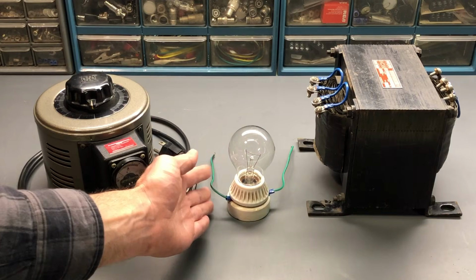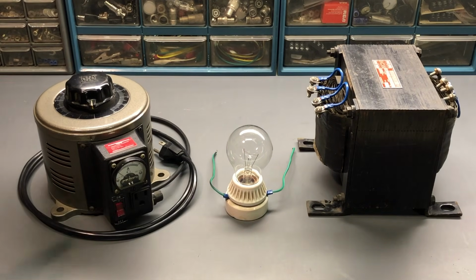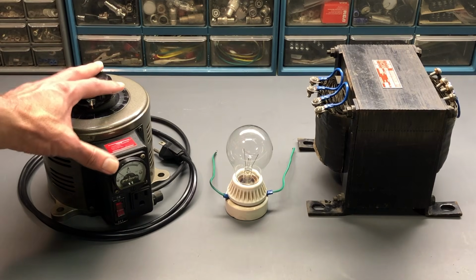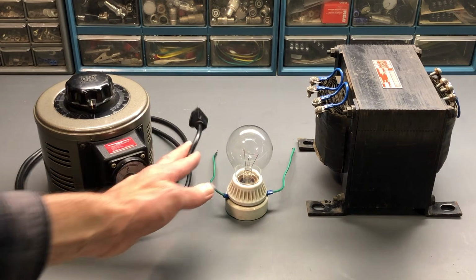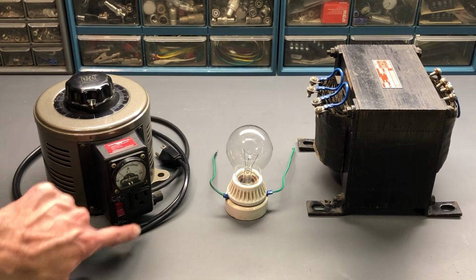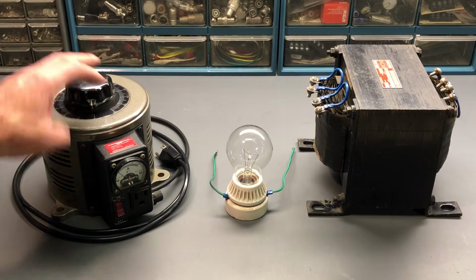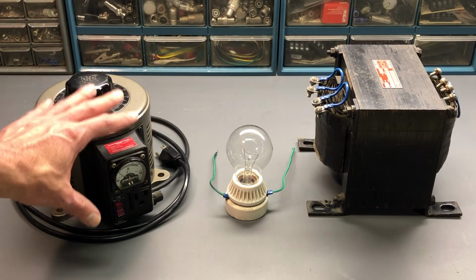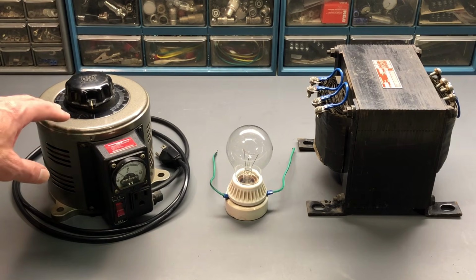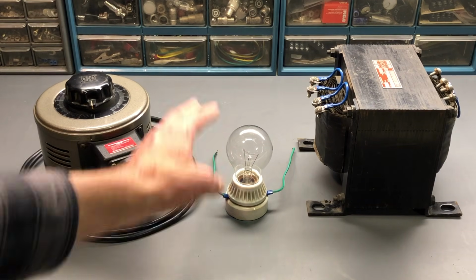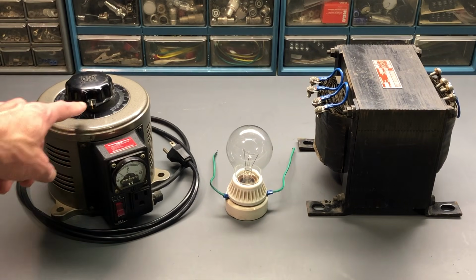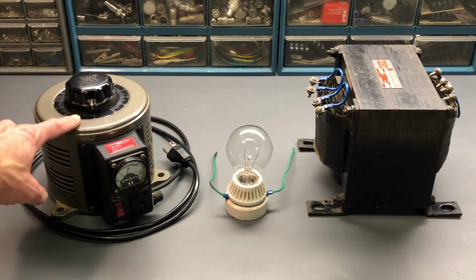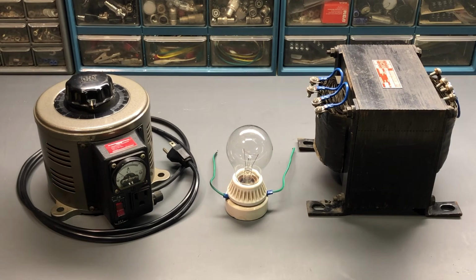Any wiring needs to be properly insulated, and many Variacs are available like this, where they're sort of an all-in-one. This has a cord on the Variac, so it can be plugged in, and you have an outlet, a switch, and an amp meter. So this is an all-in-one solution for a Variac, but again, it provides no electrical isolation. If you use a Variac like this, you may need to modify the cord or wire it in permanently. Variacs are also available that are not in a housing. They could be panel mounted or mounted in a separate type of chassis. So again, that's a personal preference on how you want to make the final installation. But again, these are the main components that would be required in an isolated dim bulb tester.